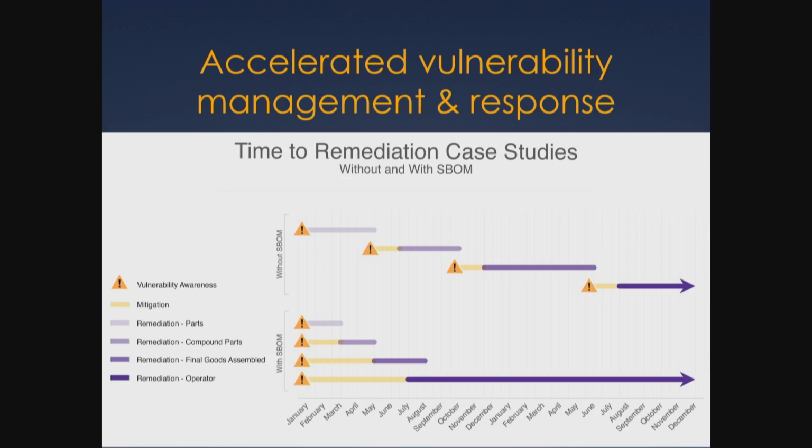That little exclamation point is the first moment of notification for those medical device makers. They do some initial triage. They take it in, they test it, they fix it, they put it through their quality process, they check in with the regulator, they push it to the hospitals. So it's a multi-legged relay race that spans actual years, and we took the numbers from that actual disclosure.